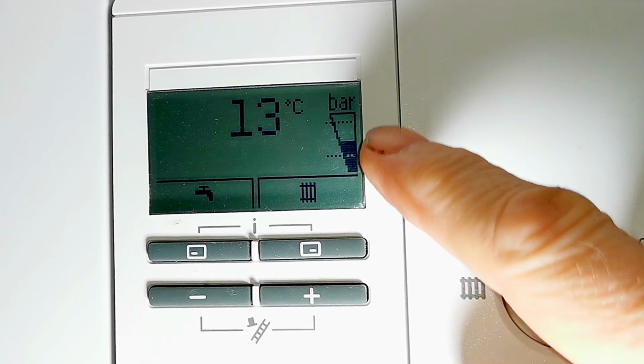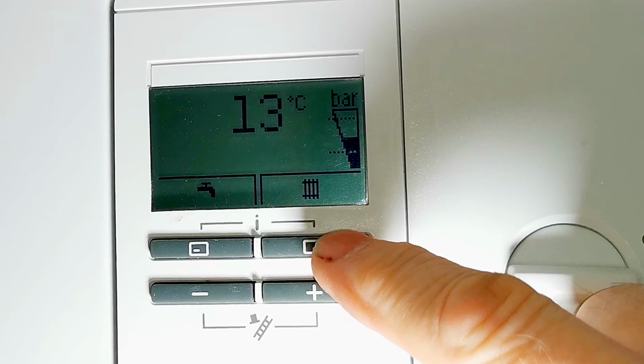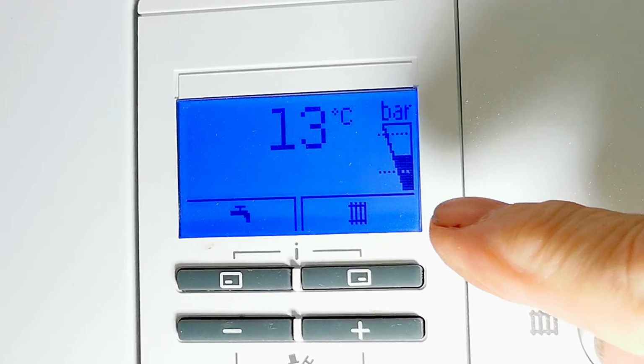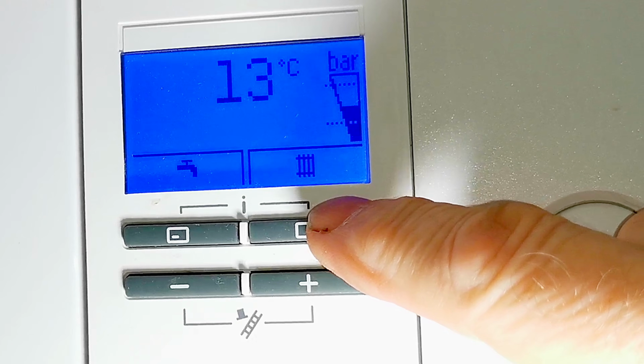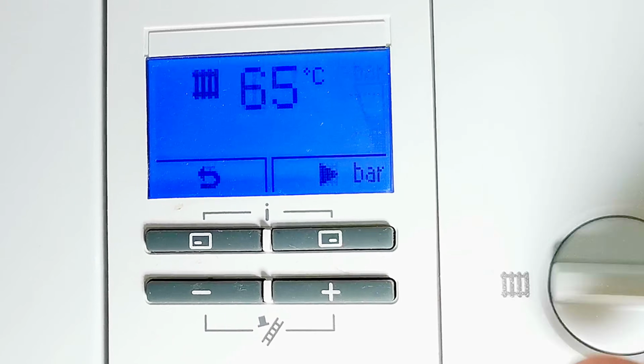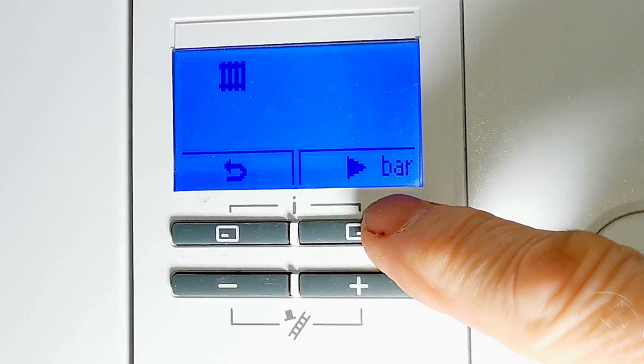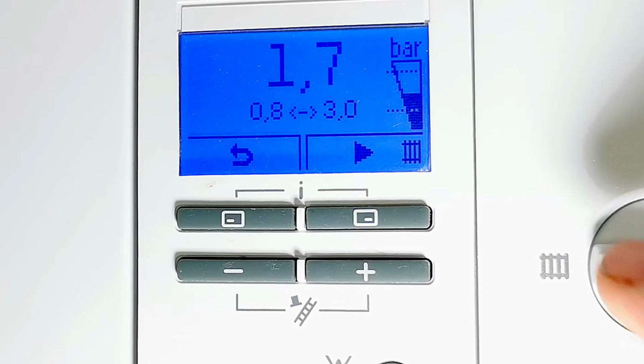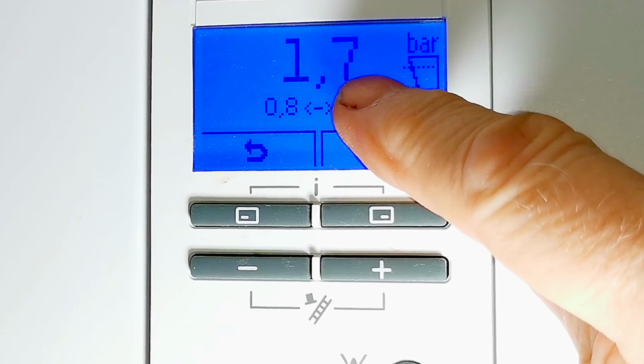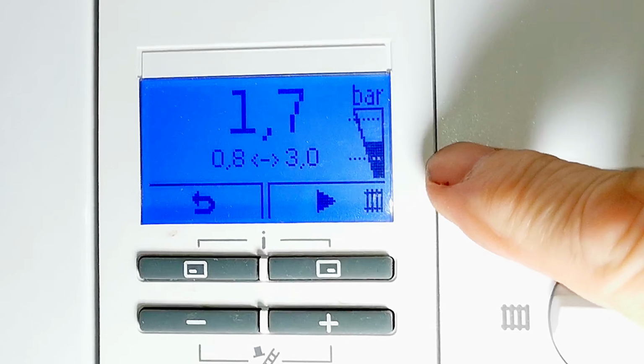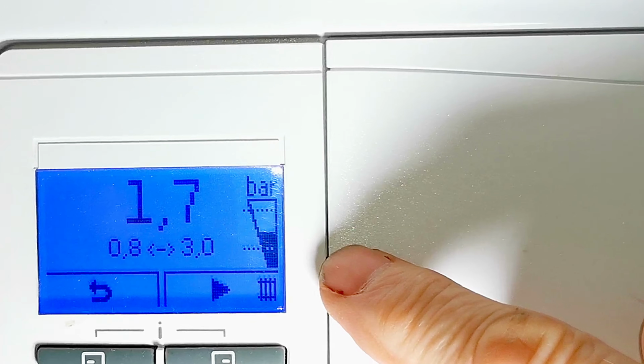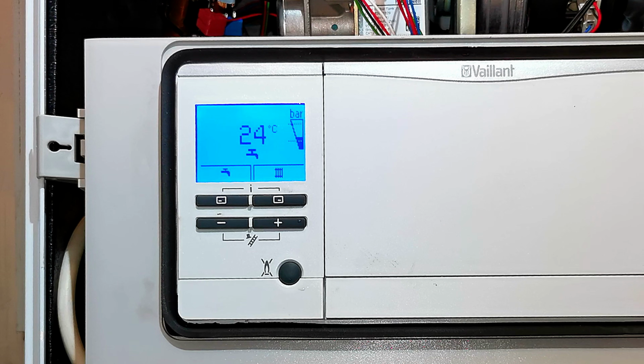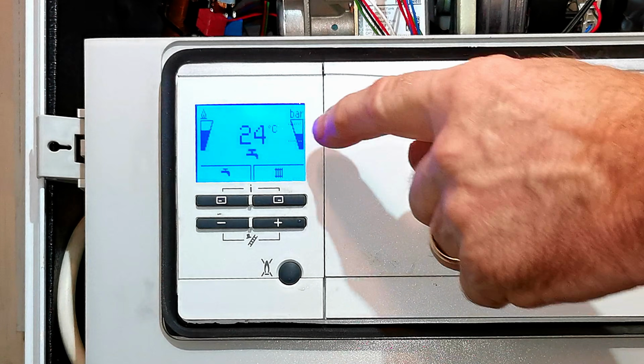If you have a Vaillant which only has a digital display, then we're looking to get that black bar level to about the middle of the display. And if we want to check how much pressure exactly is in the boiler, if we press the button underneath the radiator symbol, then we press it again, it then takes us to the display which shows us exactly how much pressure is in our boiler, which in this case is 1.7 bar. And there we go, the boiler's back up and running now, and now I've got a happy homeowner because they're no longer getting that F75 fault.